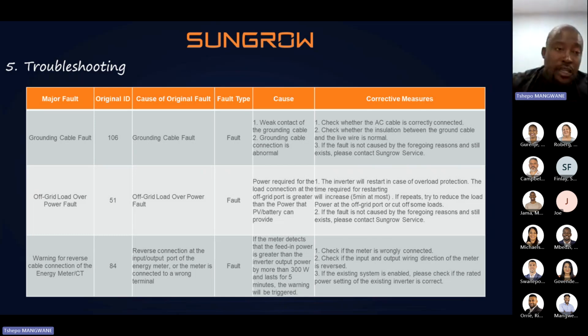Okay, so I will touch base on a few of them. And obviously, the moment there's a fault on the system, it will give you a fault code and the corrective measures to resolve that issue. All right. So the first one here, I have grounding cable fault detection. Original ID, it will appear on the inverter as 106. Original cause of the fault, it will be a grounding cable fault. Fault type is not an error, it's a fault. The system is completely in red fault mode.